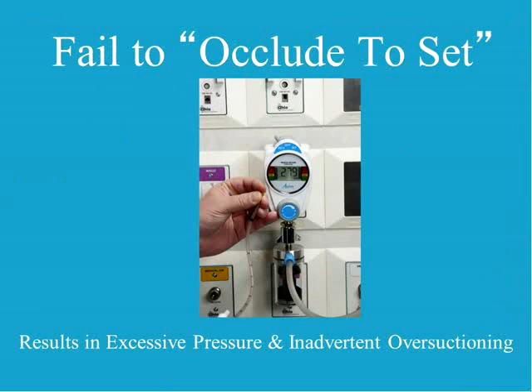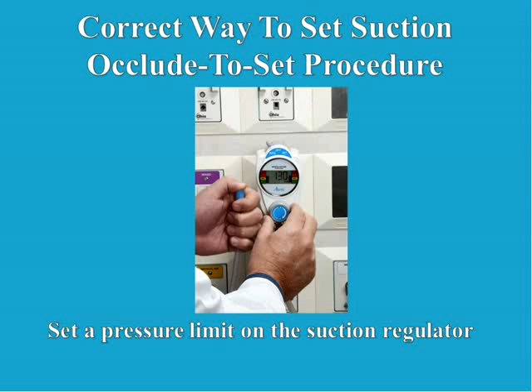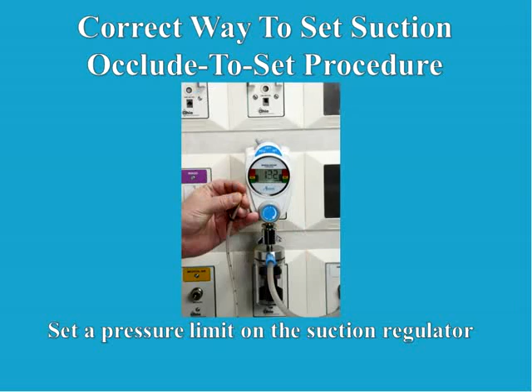The correct way to set a vacuum regulator is to occlude the end of the tubing and while it's occluded, set the appropriate vacuum pressure. So we've got 130 millimeters of mercury here. And then when you do the same exercise and occlude the catheter, you still have 130, maybe 132. So it's very important that you occlude the tubing when you set the vacuum regulator. In fact, I like to actually occlude the tubing back up at the vacuum regulator just in case there's a leak in the suction canister system or the tubing. And if that's corrected later, it could result in inadvertent oversuctioning by too much pressure. So, again, that's a preference thing.